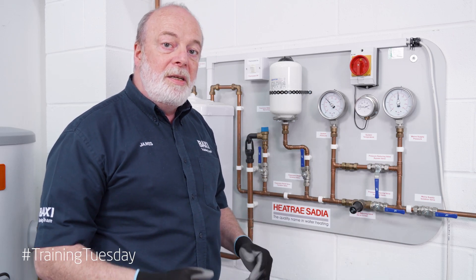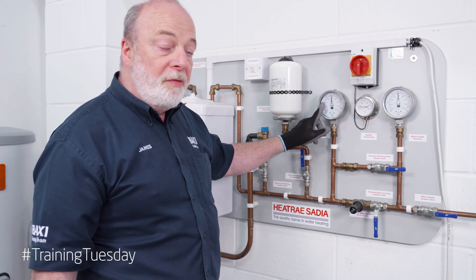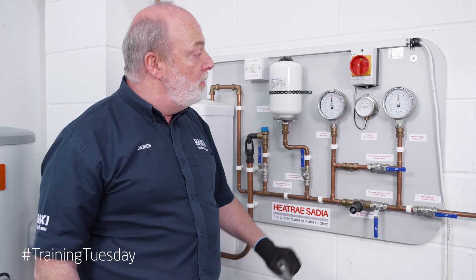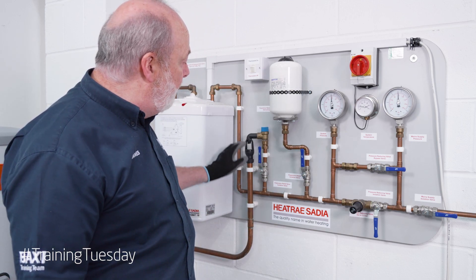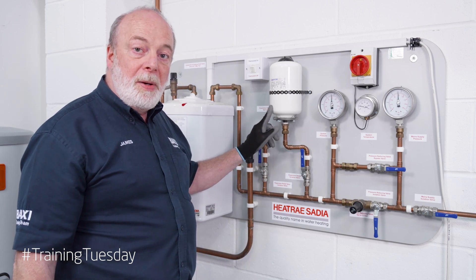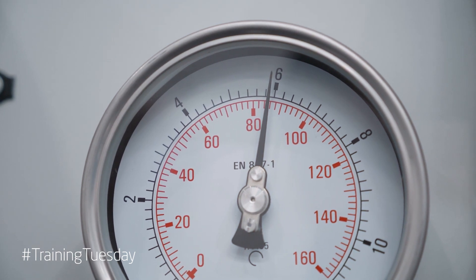What happens if we start to lose certain safety devices? Let's remove our pressure reducer first. All of a sudden we've gone from 3.5 to over 5 bar. Our pressure has gone up beyond where we want it to be, but that's okay — we're still heating the water. We still have our expansion vessel and other safety devices including our PRV and T&P valve. But what happens if we lose the ability to take up the expansion of the water? As you can see, the temperature is rising and the pressure is also rising quite fast.